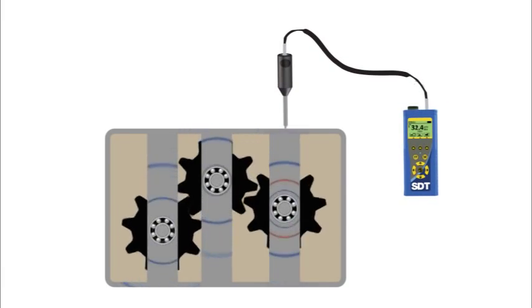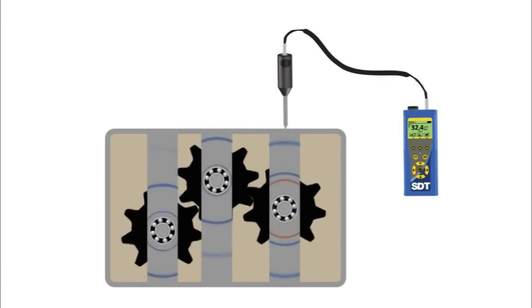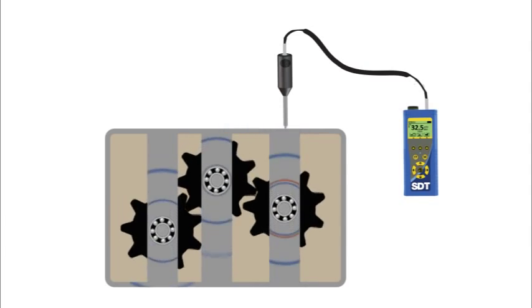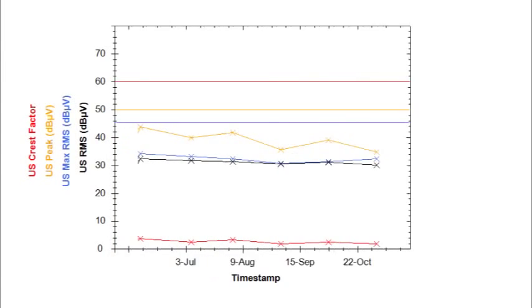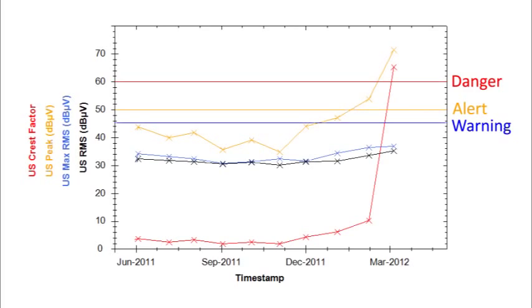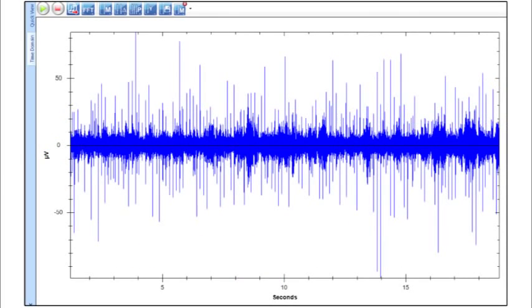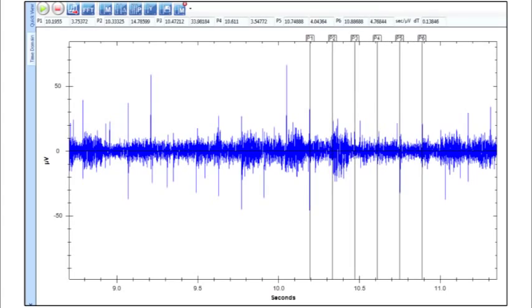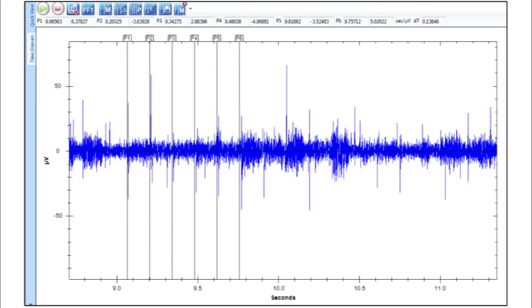Even with all the background noise in your plant, the SDT 270 hears only the bearing's ultrasound. It measures and records it to let you predict and plan your next maintenance move. Static signals are measured as decibels and trended against previous values and preset alarms. Dynamic signals are recorded and analyzed in the time and frequency domain for in-depth analysis of fault conditions.